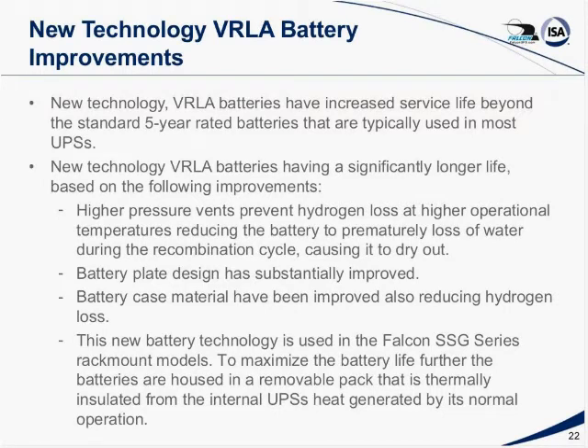The new technology batteries have higher pressure vents. One of the major problems with valve-regulated sealed lead-acid batteries is that at higher temperatures, hydrogen is lost through the vents. If they're the low-pressure vents that are used in most batteries, typically rated about 2 to 5 pounds per square inch, hydrogen is lost. When the battery goes through its recombination cycle, it's lost hydrogen, it can't produce as much water, and so the batteries over time dry out.